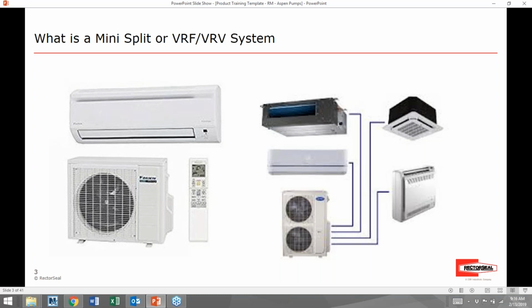That picture on the right-hand side shows what might be a typical commercial installation. That's kind of how we identify VRV versus mini split. Mini split on the left is typically a residential or light commercial application with one indoor unit to one outdoor unit, although some units may have 2 or 3 indoor units to one outdoor unit. On the right-hand side, you see what might be a VRF machine with 4 different types of indoor units or heads. The 2 we're going to focus on today are the high wall unit here directly above the unit and the ceiling cassette there on the top right of that picture.